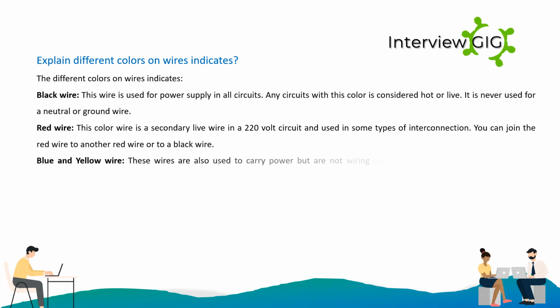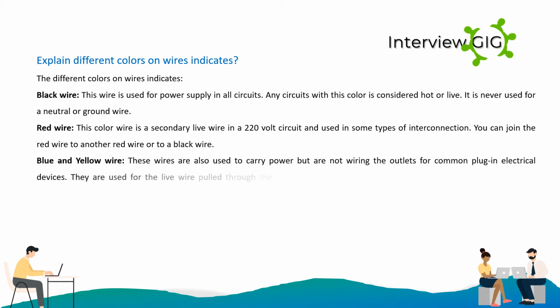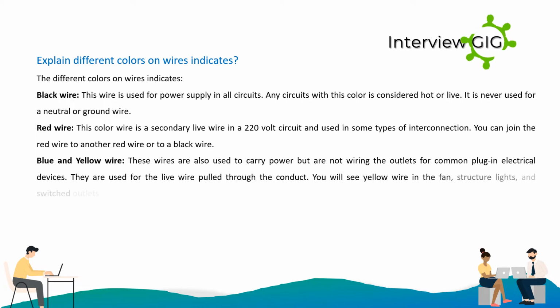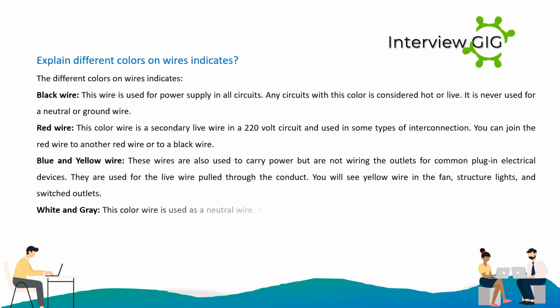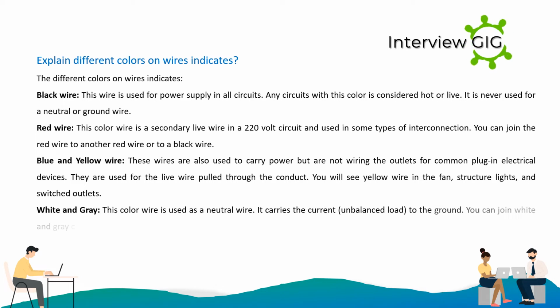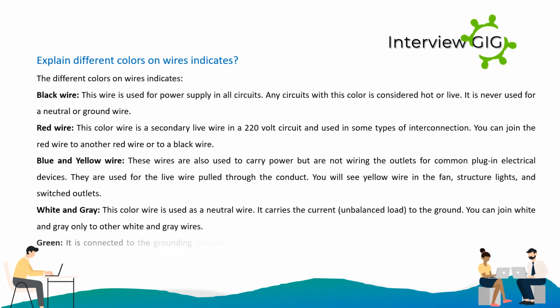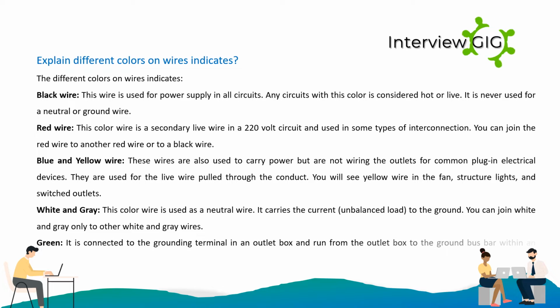Blue and yellow wires: these wires are also used to carry power but are not wiring the outlets for common plug-in electrical devices. They are used for the live wire pulled through the conduit. You will see yellow wire in the fan, structure lights, and switched outlets. White and gray: this color wire is used as a neutral wire. It carries the current, unbalanced load, to the ground. You can join white and gray only to other white and gray wires. Green: it is connected to the grounding terminal in an outlet box and runs from the outlet box to the ground bus bar within an electric panel.